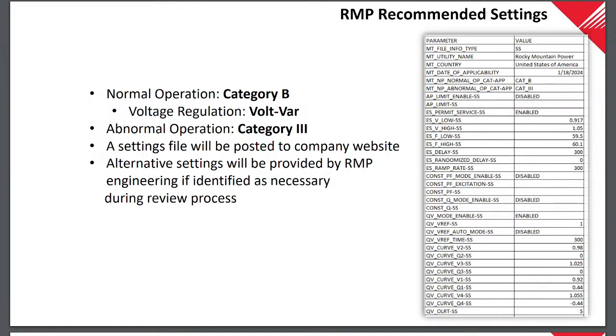When it starts to consume vars, the current at our circuit level goes up, and it starts to overload even more of the circuit. So at that point, that volt var setting actually hurts another part of the circuit. Even though it might lower the voltage, which is what it's supposed to do, it's going to overload the circuit. So in that case, it's not the right setting to use. We'd have to look at another mode that would help the voltage without overloading the circuit.